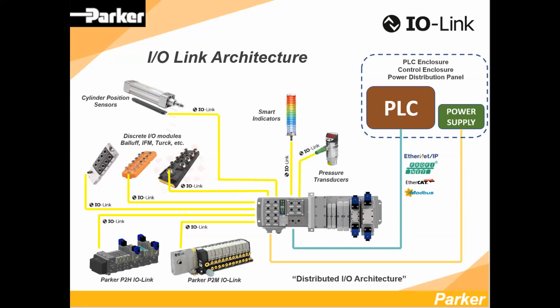So basically then you're getting out to the IOLink Masters, out to either the network modules, sensors of some sort - pressure sensors, linear encoders, lasers, ultrasonics, whatever kind of sensors - right down through to prox sensors or whatnot, which are normally still connected to your IO hubs, your IO blocks. Cylinder switches, instead of getting a discrete work home or extend/retract signal, you're actually getting an analog representation of where that cylinder is.